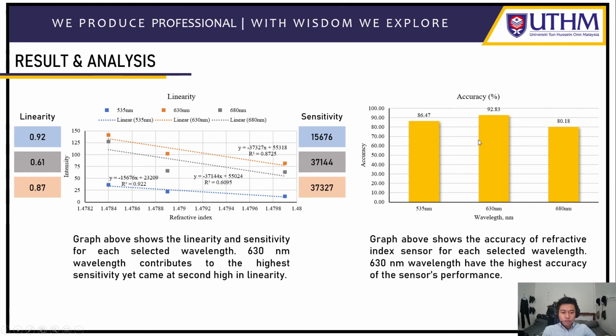For graph accuracy, the graph above shows the accuracy of the refractive index sensor for each selected wavelength, which is 535 nanometer, 630 nanometer, and 680 nanometer. As you can see here, the 630 nanometer wavelength has the highest accuracy of the sensor's performance.